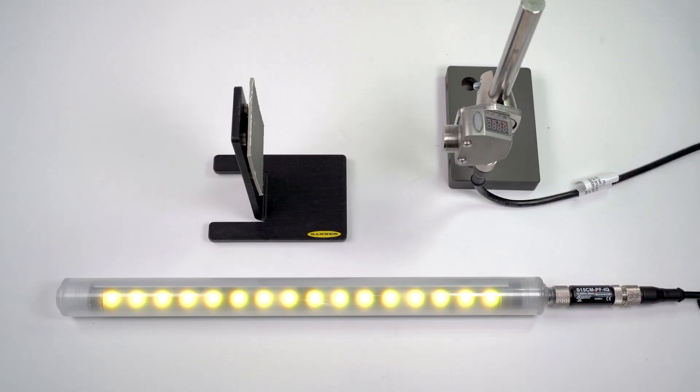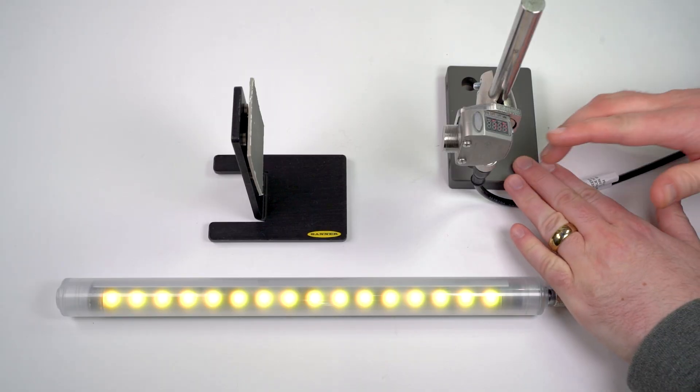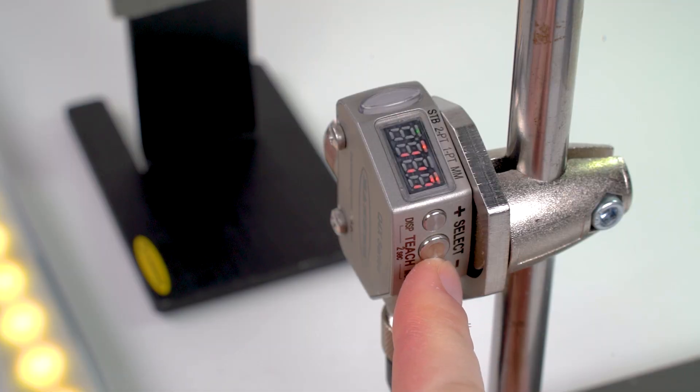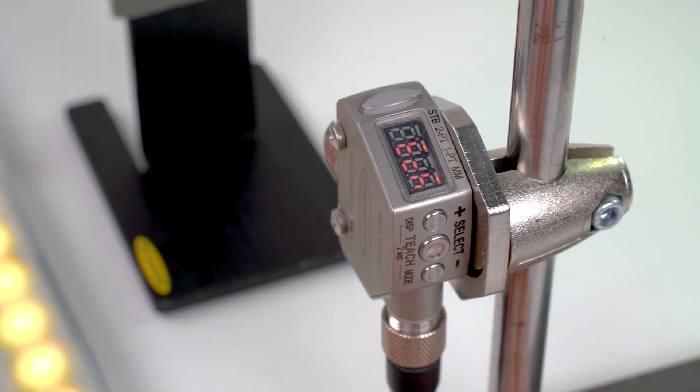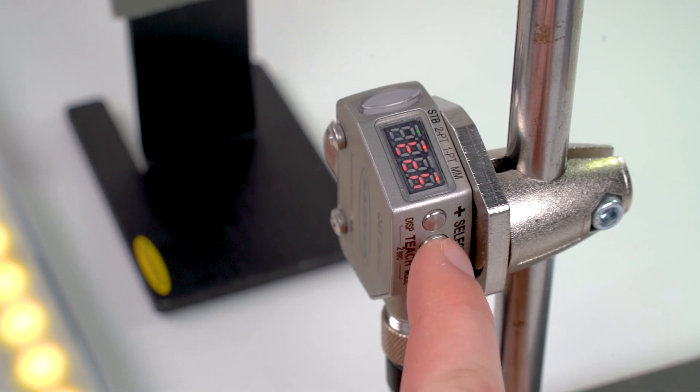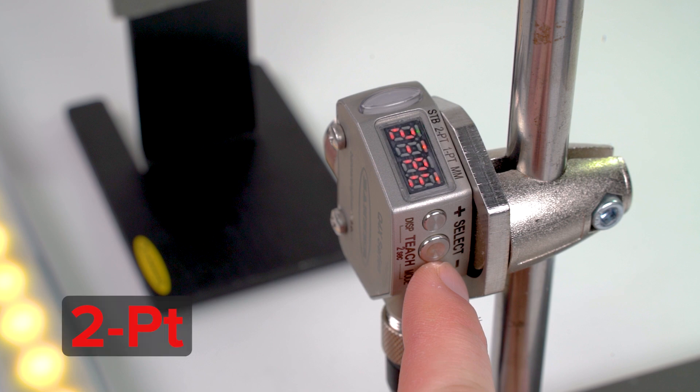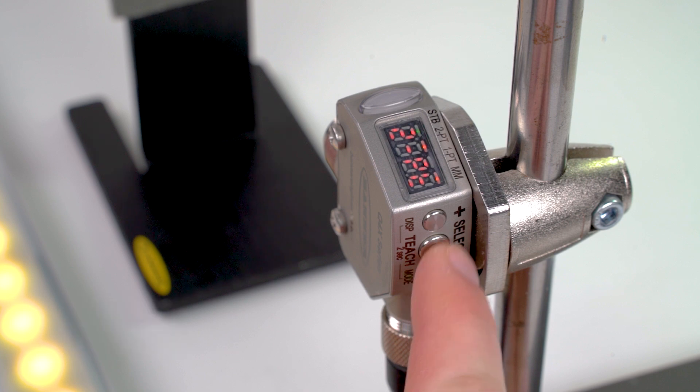The first step is to select the teach mode from the setup mode menu. Press and hold the minus or mode button for two or more seconds. The menu will show TCH. Press the select button to enter the teach selection menu and use the plus and minus buttons to navigate through the options until you see the two-point option and press the select button again.